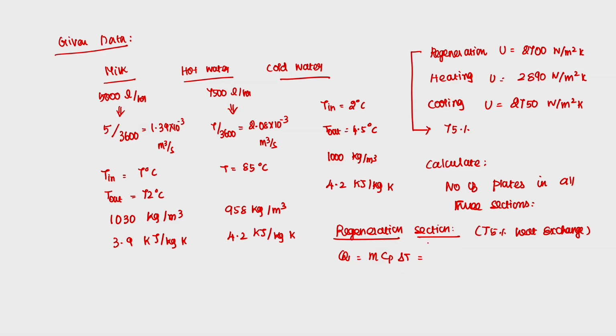The mass flow rate is not directly given; only volumetric flow rate is given. So, 1.39 into 10 to the power of minus 3, into density, which is 1030, and Cp given as 3.9 into 10 to the power of 3 joules, and the total temperature gradient is 72 minus 7, which is 65. So, the total Q comes out to be 3.6 into 10 to the power of 5 watt.